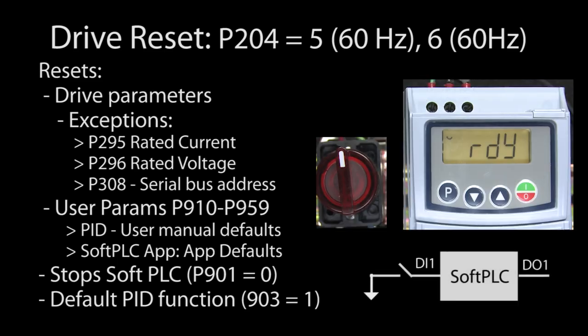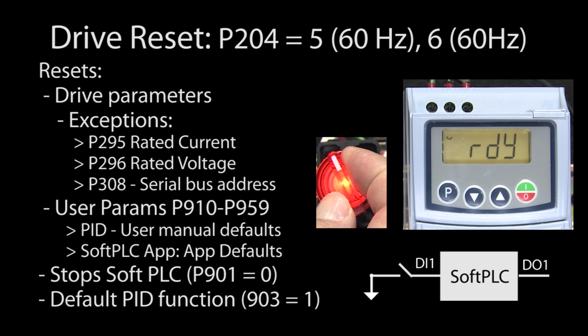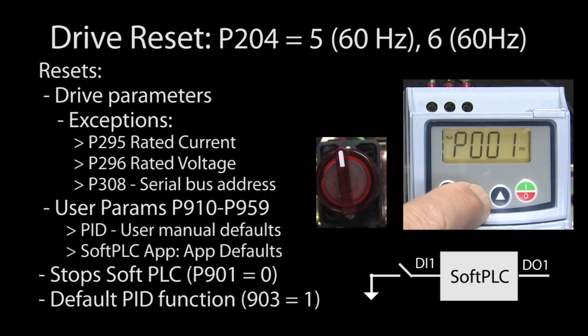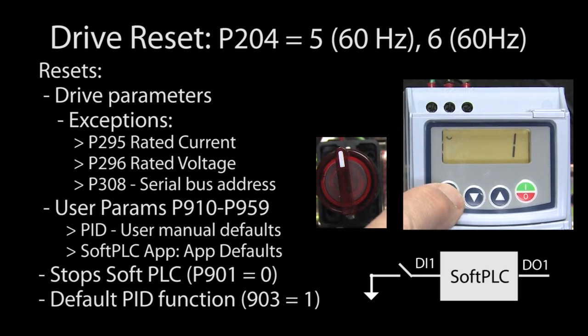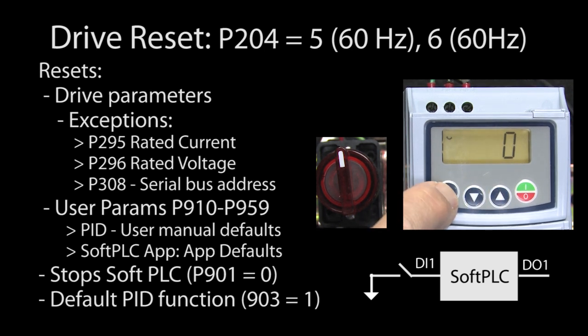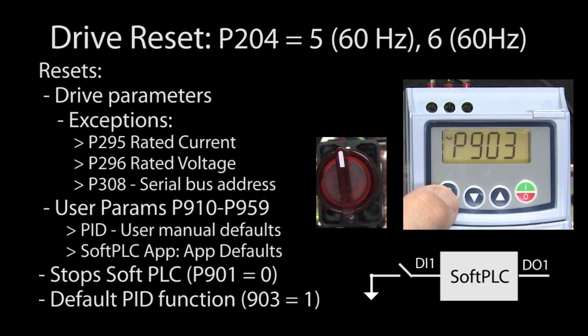For example, I have a simple soft PLC app running that lights this indicator to show me what the state of the switch is. I see parameter 901 is a 1, which means the soft PLC app is running, and parameter 903 is a 0, which means I am using a soft PLC app and not the built-in PID function.